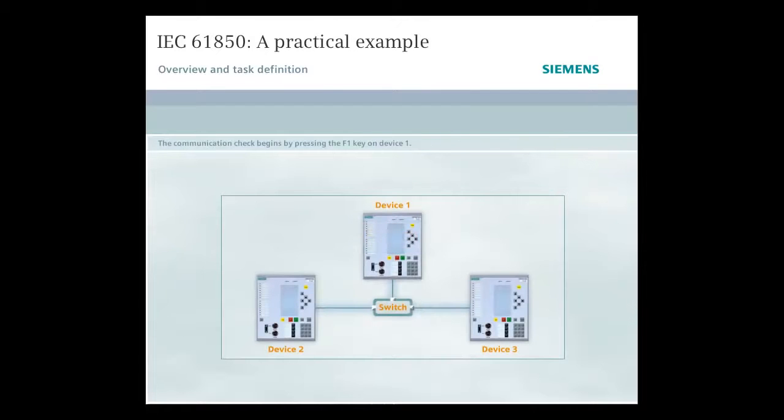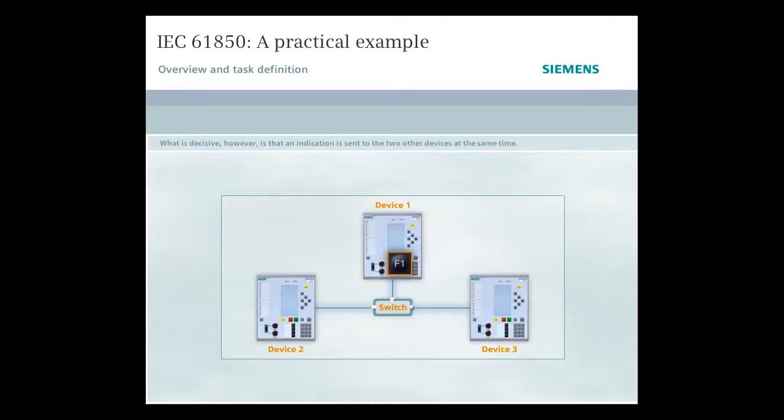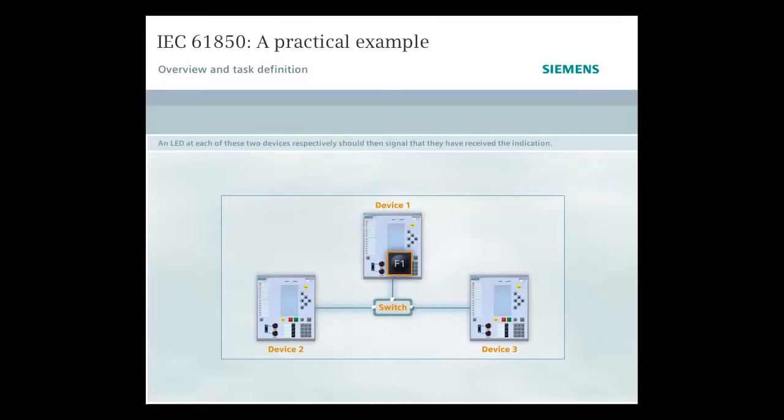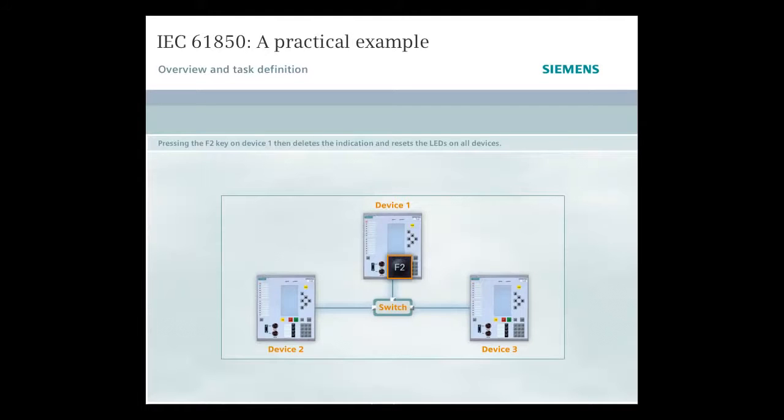The communication check begins by pressing the F1 key on device 1. The fact that LED1 lights up on the same device confirms that it has been pressed. What's decisive, however, is that an indication is sent to the two other devices at the same time. An LED at each of the two devices respectively should then signal that they have received the indication. Pressing the F2 key on device 1 then deletes the indication and resets the LEDs on all devices.